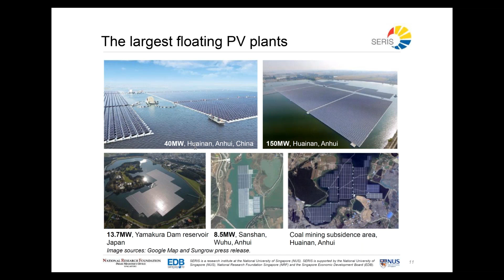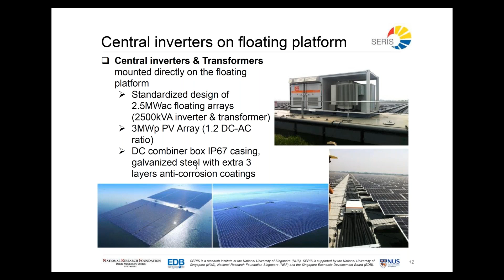The industry has grown to a level where you can buy off-the-shelf, say, 2.5 megawatt floating solar arrays, which come with the floating structure, the PV panels, the DC interconnects, and there are even manufacturers providing central inverters on a floating structure, including the transformer, with a 20 or 22 kV connection to land. This, again, is to build trust and bring across the message that this has reached a state of being a very professional industry, and deployment is now more about project development and finding the most suitable pieces of land.